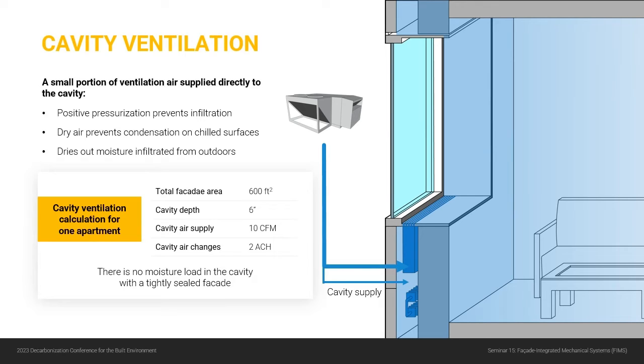Now, part of making this work requires you to actually supply air into that cavity. So we have this ductwork running in the facade, supplying this conditioned air to the space. So you can take just a little bit of that air and actually supply it directly into the cavity. And that does a few important things for us. It positively pressurizes the cavity to prevent infiltration from outdoors. And it also keeps that cavity nice and dry. And that's how we prevent condensation on those chilled surfaces, those chilled water pipes within the cavity.